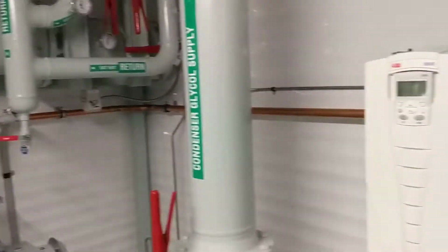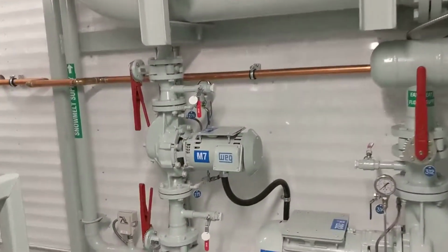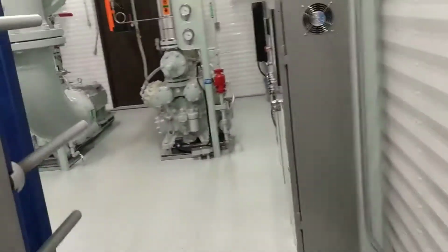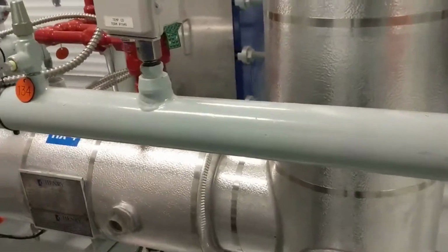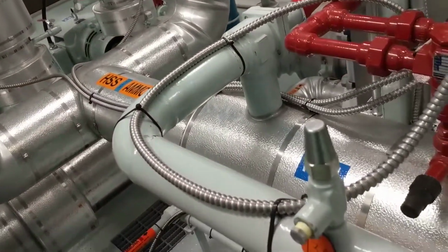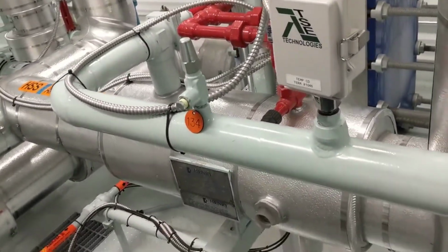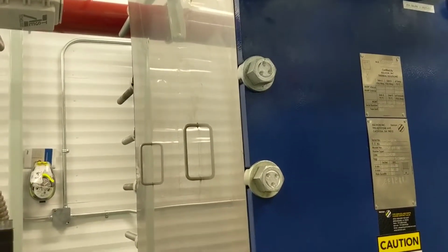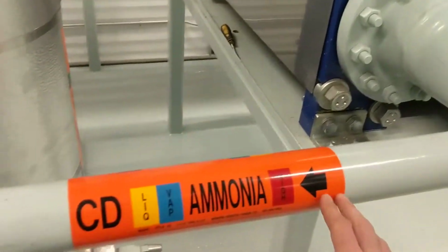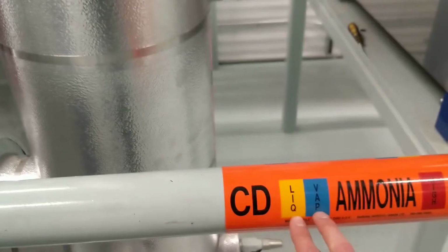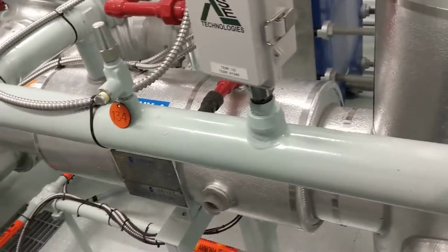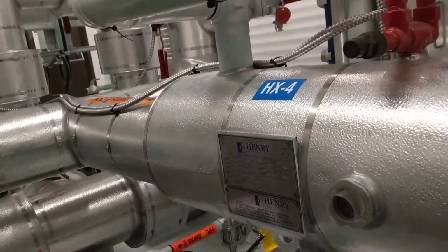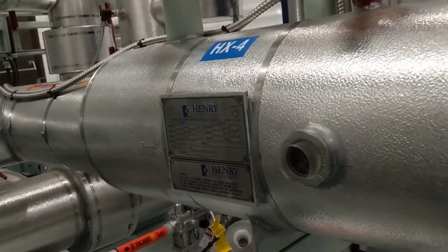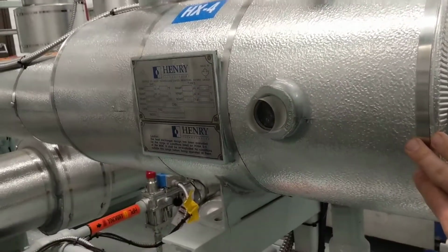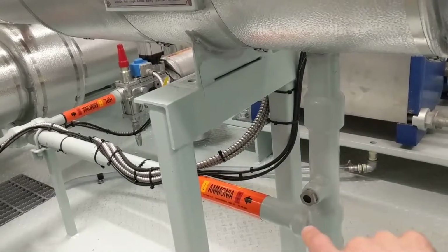The other one that we should look at is this one back here. I should have talked about this one before, and that is in here, and that's HX4, and it is an ammonia heat exchanger. So coming in from the condenser, the ammonia is coming along here as a liquid and vapor, potentially. It's coming down into this heat exchanger, flooding through the heat exchanger. This is shell and tube, and it's coming out here as liquid ammonia.